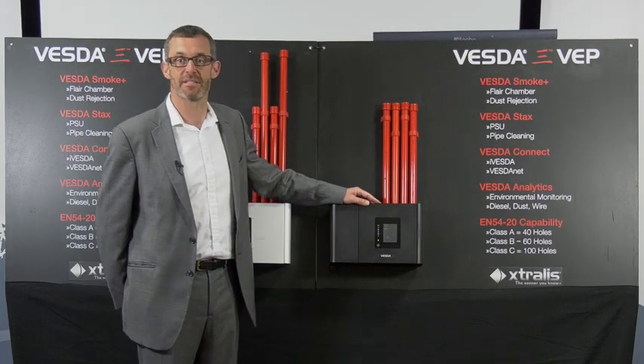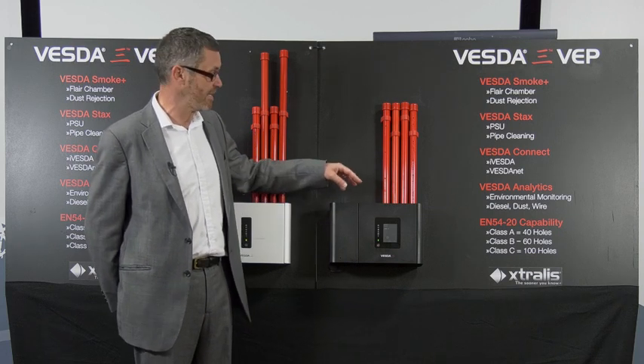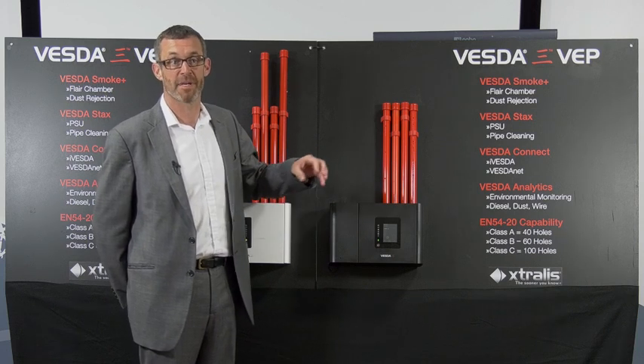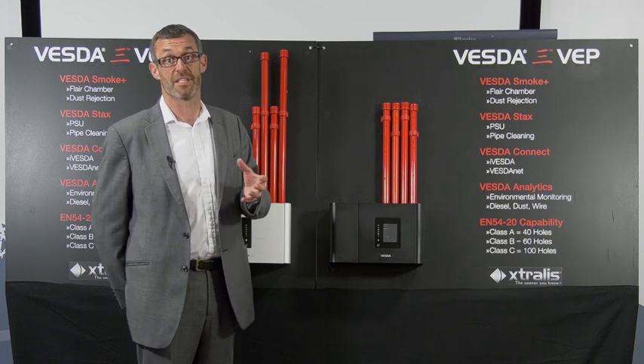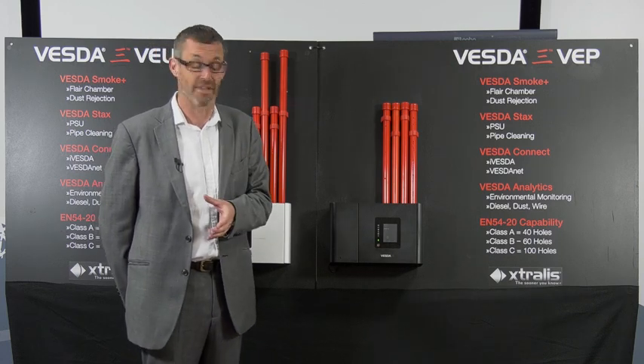The clean air bleed is unique to the way VESDA works and it's critical that we have the clean air bleed to maintain the integrity of the detection chamber inside. If the detection chamber becomes contaminated with dirt it will affect its performance and we'll have to adapt the detector's performance to compensate for that.